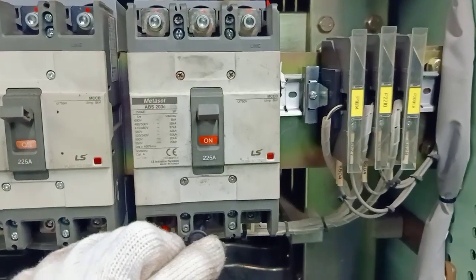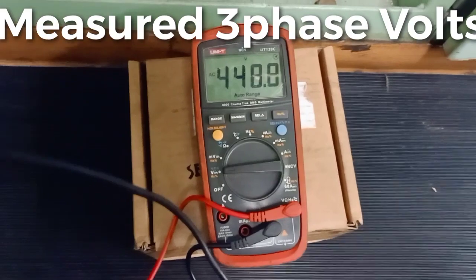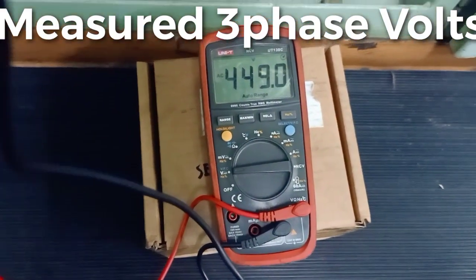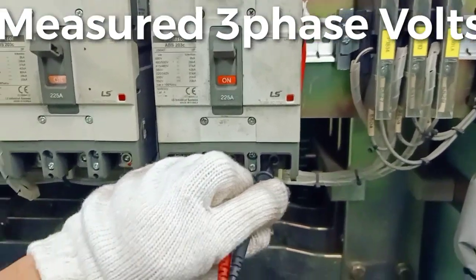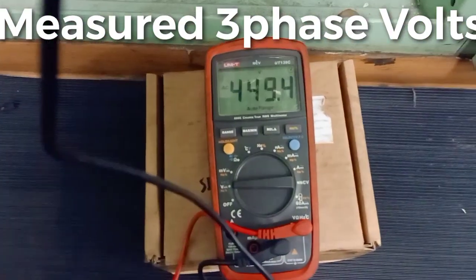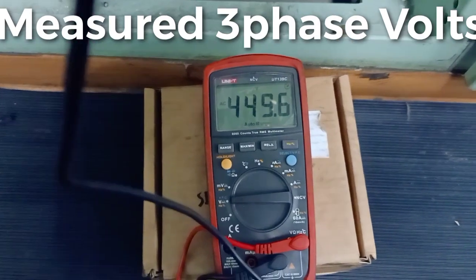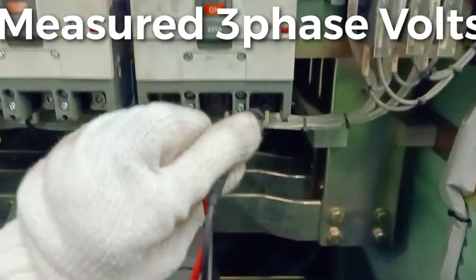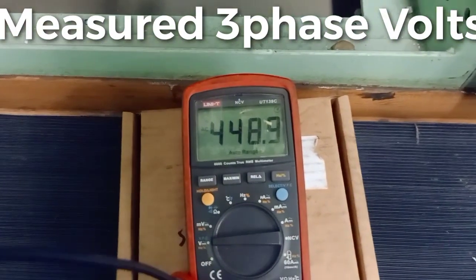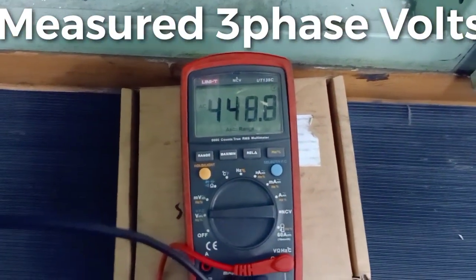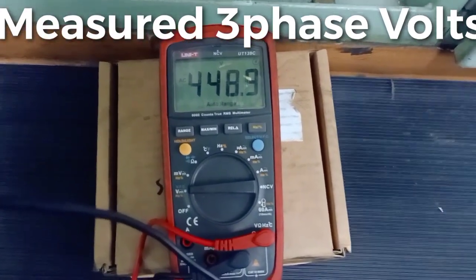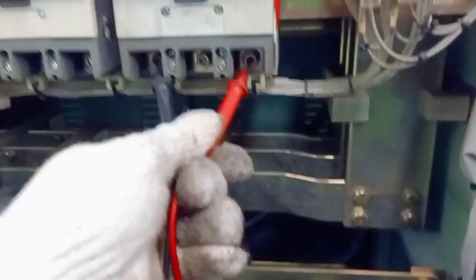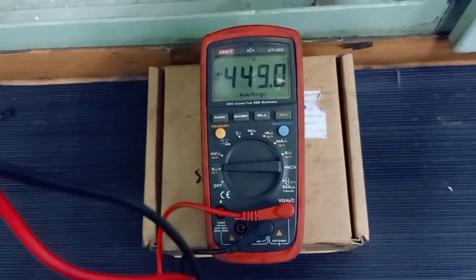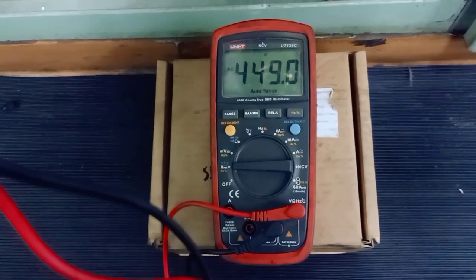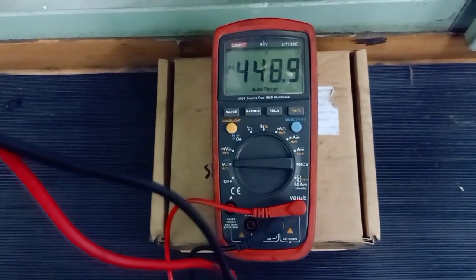Final test now. Switch on. Test the load side voltage. Now this is normal. It's 440 volts. It's working now normally. Next one. Same. It's 449 volts. Last one. So it's 448 volts. Now it's confirmed. Line 1, line 2, line 3 are all working normally.